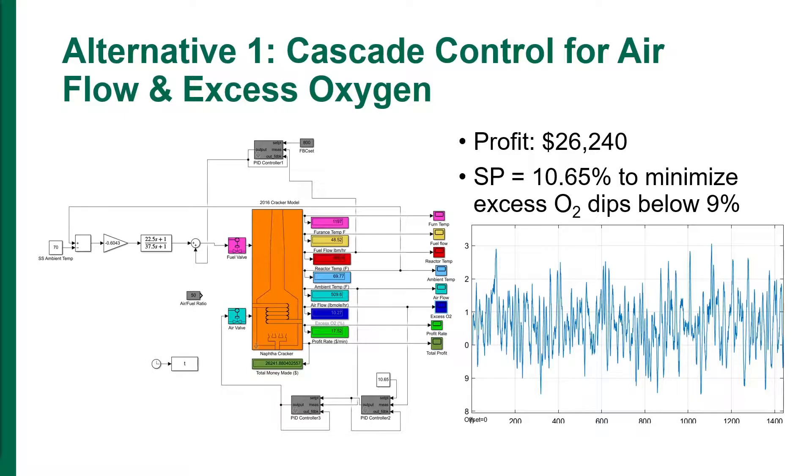Two alternative control schemes were considered to control the excess O2. In the first alternative, the ratio control was replaced with the cascade control. The inner loop, PID controller 3, controls the air flow, while the outer loop controller, PID controller 4, controls the excess O2. The profit was $26,240. While the profit was higher, the oxygen dipped below the 9% allowed value multiple times during the day. The set point had to be raised to 10.65%, but even then, the issue remained and the oxygen still dipped below the 9% six times during the day.